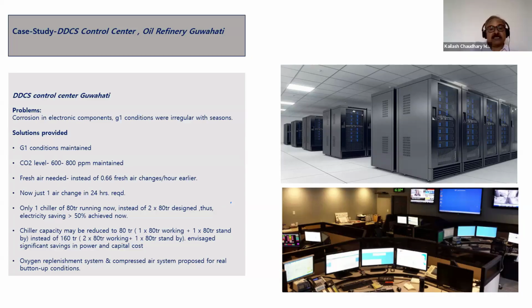CO2 levels are now actively maintained at 600 to 800 ppm, well within the optimum cognitive performance range. Fresh air exchange was drastically reduced from 0.66 air changes per hour to just one air change per 24 hours now, a fundamental shift in philosophy.